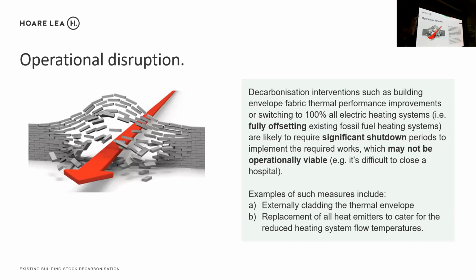Operational disruption, I think, is a real challenge for existing buildings - going to a major fabric upgrade, like externally cladding the walls, or an all-electric heat pump solution where you have to change all the heat emitters because they've been sized for higher temperatures, and potentially the pipework, which will shut the building. The jobs that we did, because of the way we tied them in - plant areas only - we kept those buildings fully operational. There was no downtime.